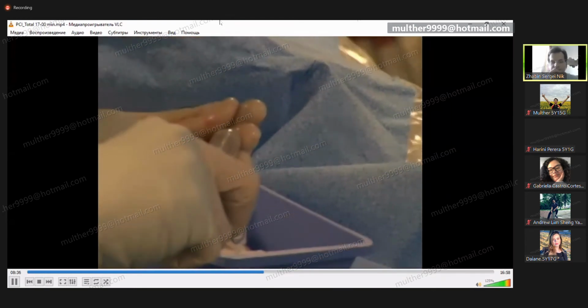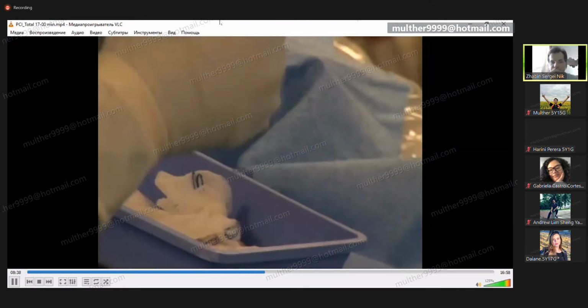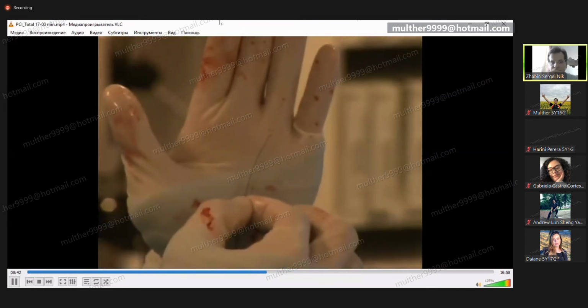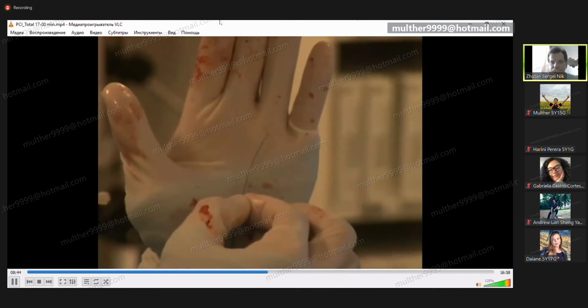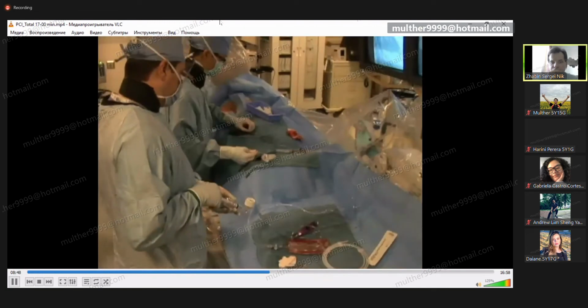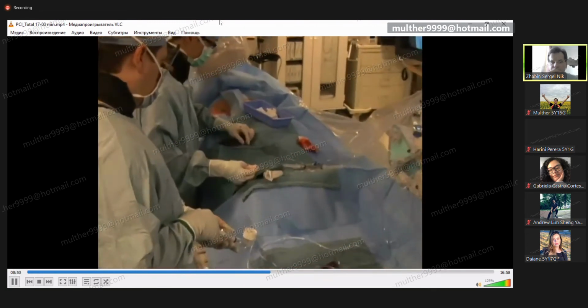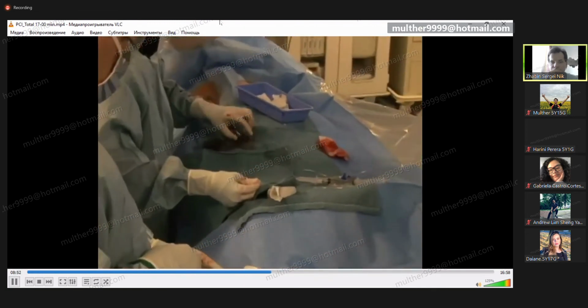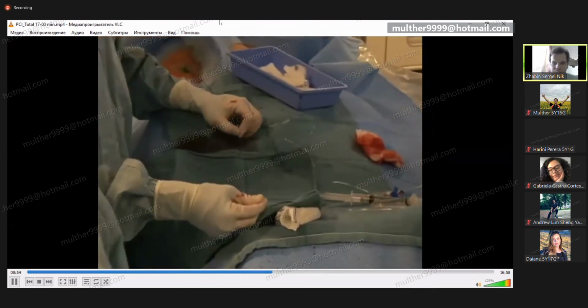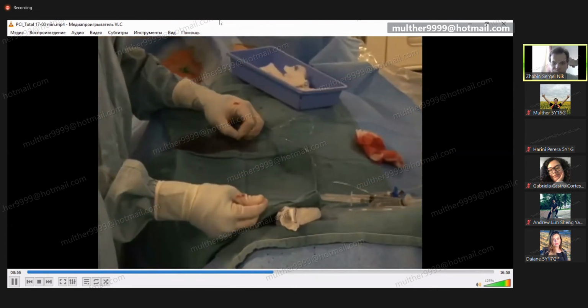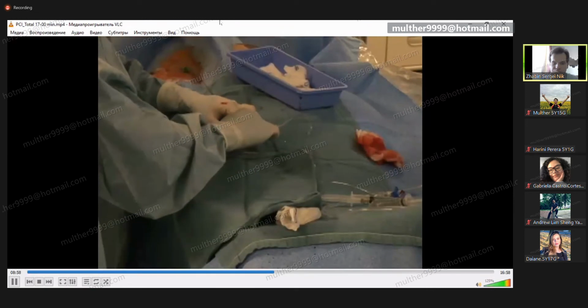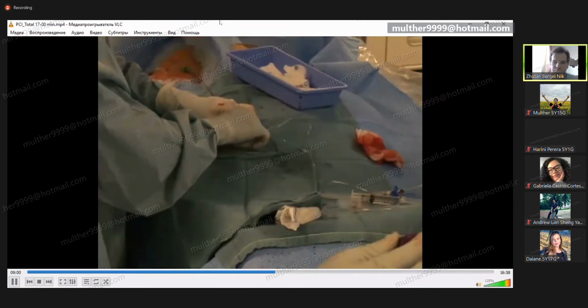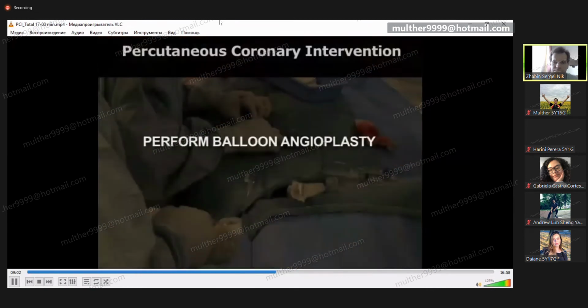Use of an angioplasty balloon catheter is demonstrated here. The balloon is on the distal end of the catheter, which has a short, approximately 10 centimeter length, monorail lumen through which the catheter is advanced over a guide wire. The balloon lumen is prepped with negative pressure, and the short monorail lumen is flushed with heparinized saline. The balloon is advanced over the guide wire into the guide catheter and to the region of the lesion under fluoroscopy.